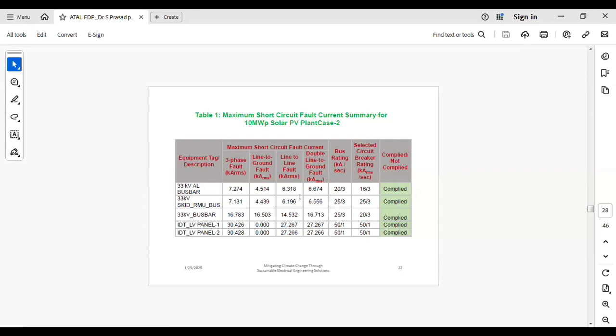Selected circuit breaker rating: what is the circuit breaker rating connected at this bus? 16 kiloampere for 3 seconds. Its withstand capacity is 16 kiloampere, and it can withstand for 3 seconds. Similarly, 25 kiloampere for 3 seconds, 20 kiloampere for 3 seconds, 50 kiloampere for 1 second, 50 kiloampere for 1 second. Basically, at the low voltage LV panel buses, the time considered is 1 second and the current rating will be very high, because at the LV panel the short circuiting current is very high. At the HV side, the short circuiting current will be very low.